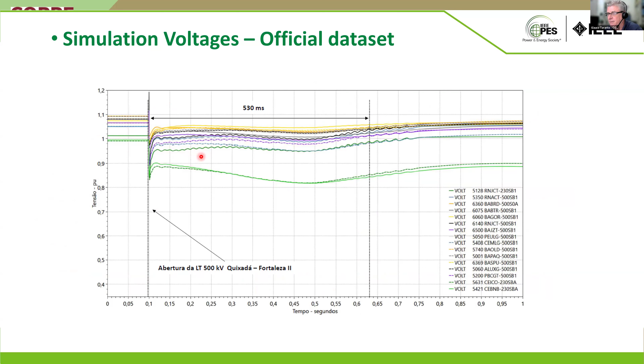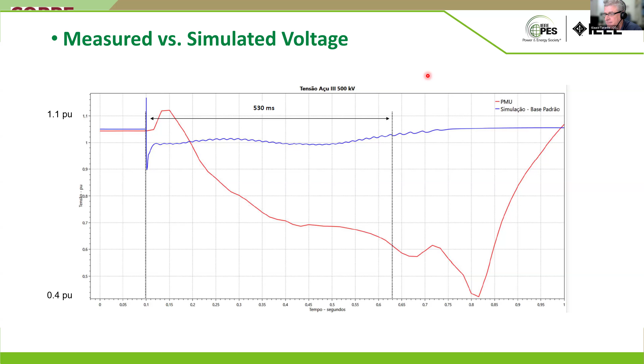and this is a voltage in this Açu III 500 kV bus. Red is PMU measurement, and blue is simulated. Then you see that the operator saw no problem with the models that they had. That's why the system should be safe, secure with respect to the models, but the reality was the red curve.